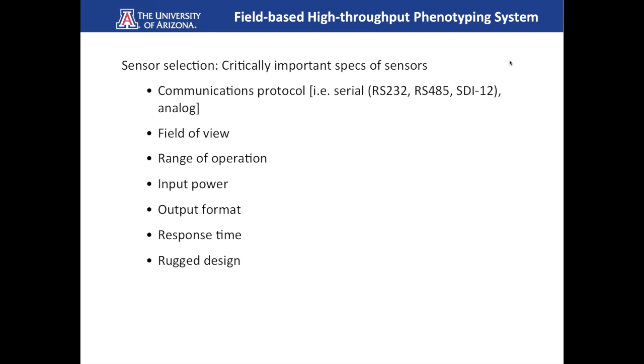On sensor selection, we've worked over a list of what we call critically important specifications of sensors, things that need to be studied before selecting one. The first we deal with all the time is communications protocols: are those sensors communicating serially or with analog signals? And if serial, is it RS-232, RS-485, or the one we see more often now, SDI-12? Those are important aspects to consider.